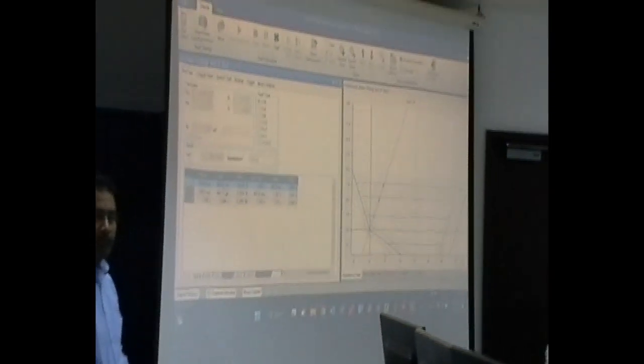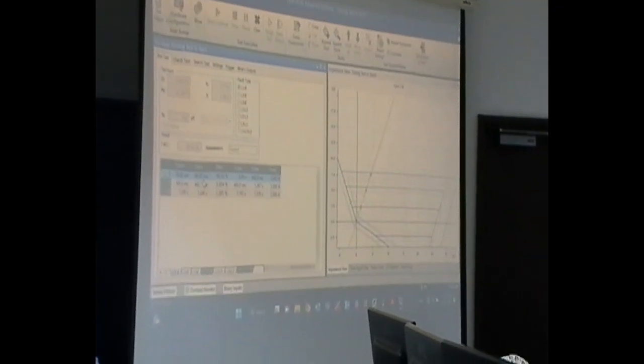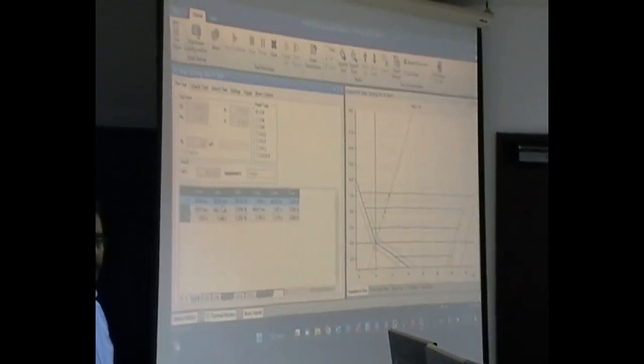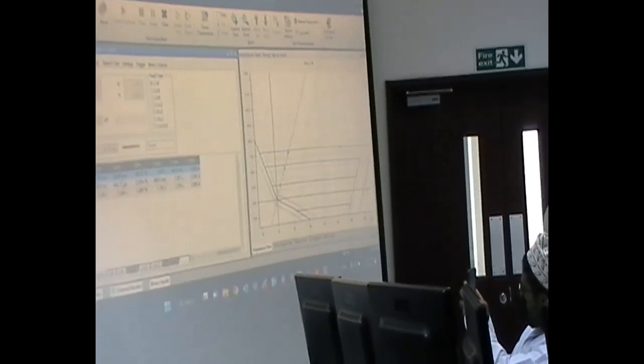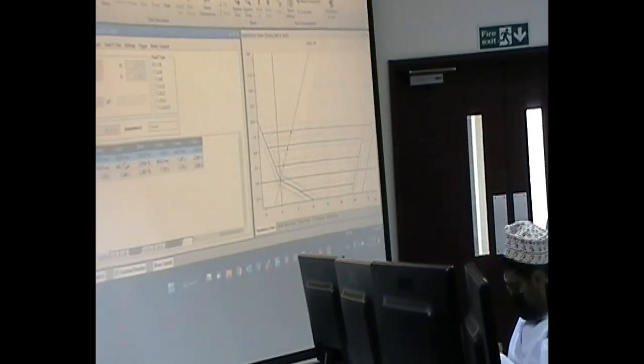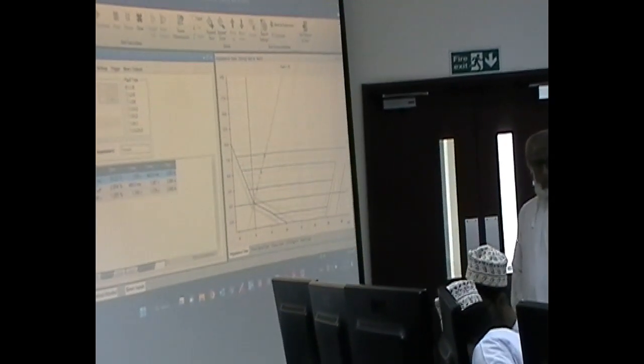Basically the relay will take at least 30 to 40 milliseconds. Even in real life, we could find the relay operated in 30 or 40 milliseconds, but again, the circuit breaker will take its own time, which is normally 60 to 100 milliseconds. For the whole tripping, it will go to about 150 milliseconds.